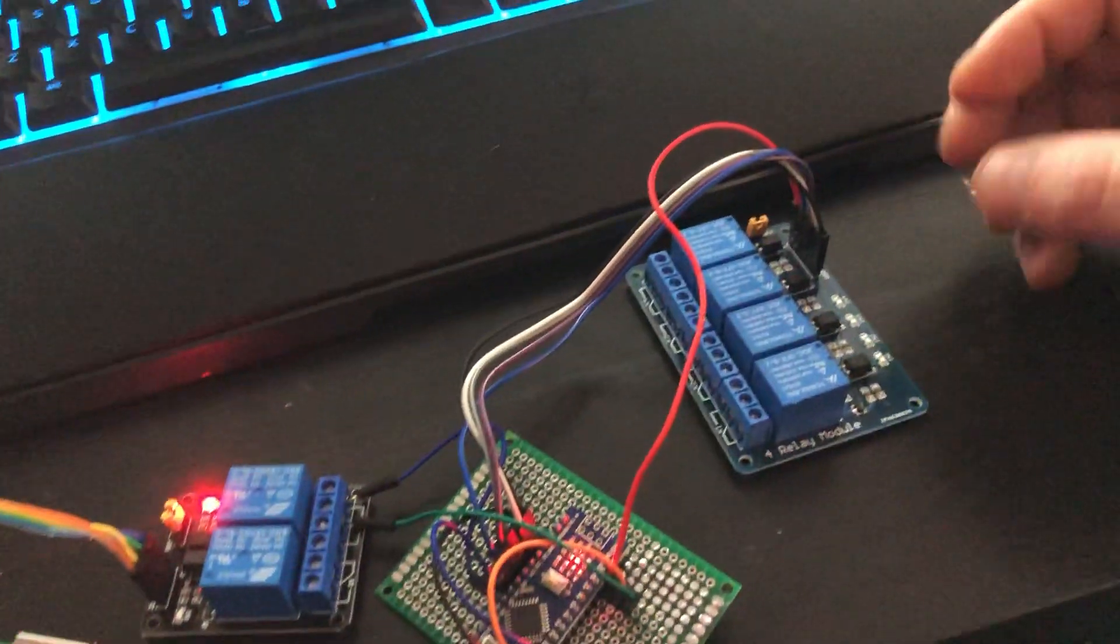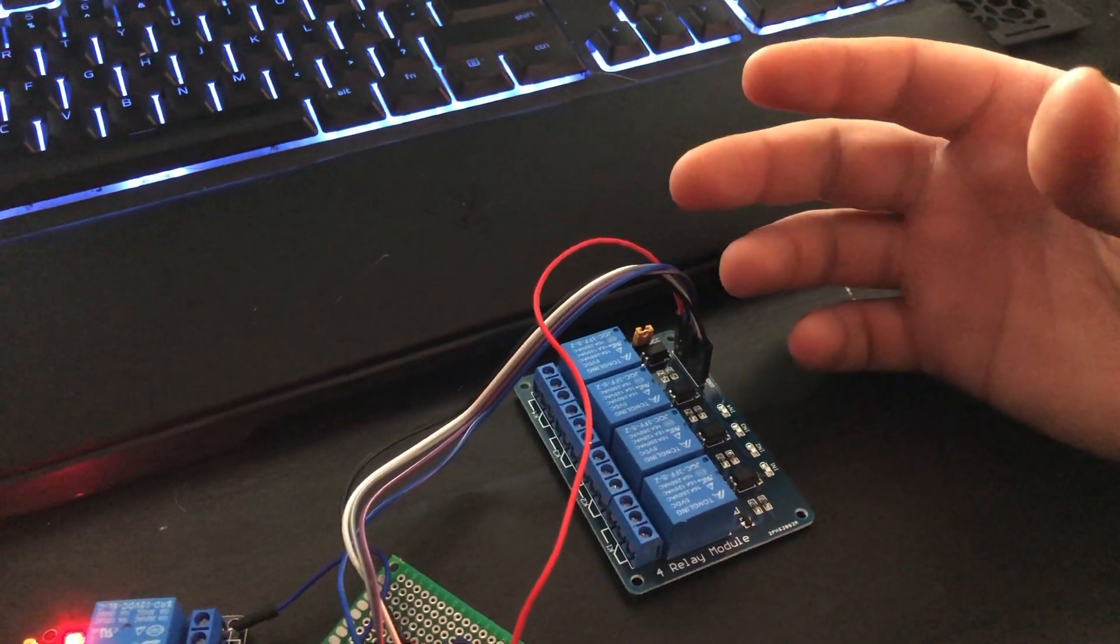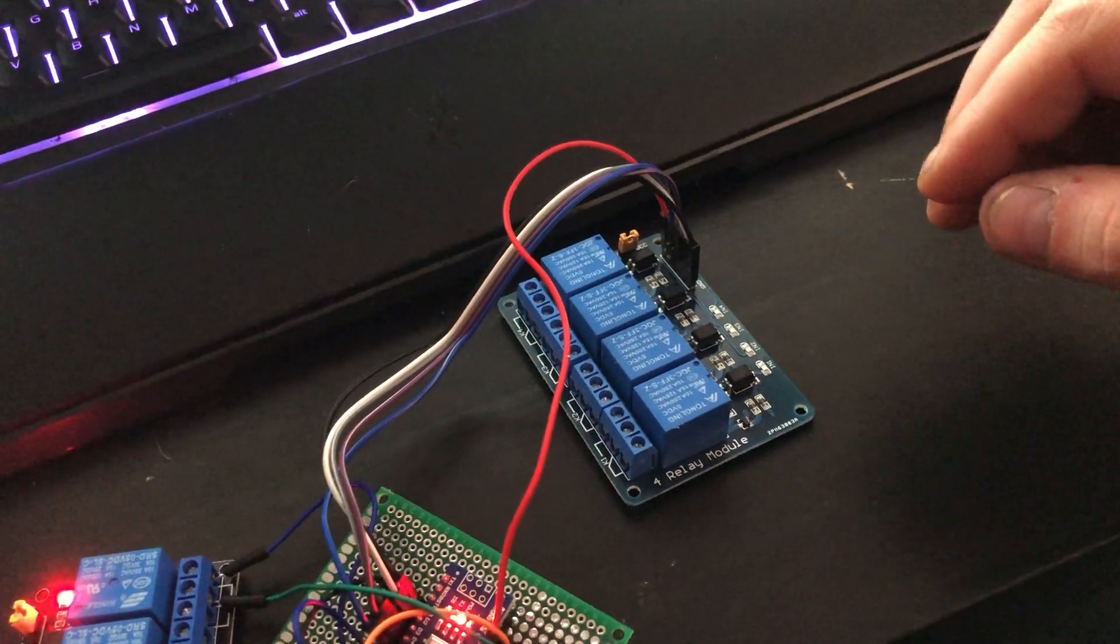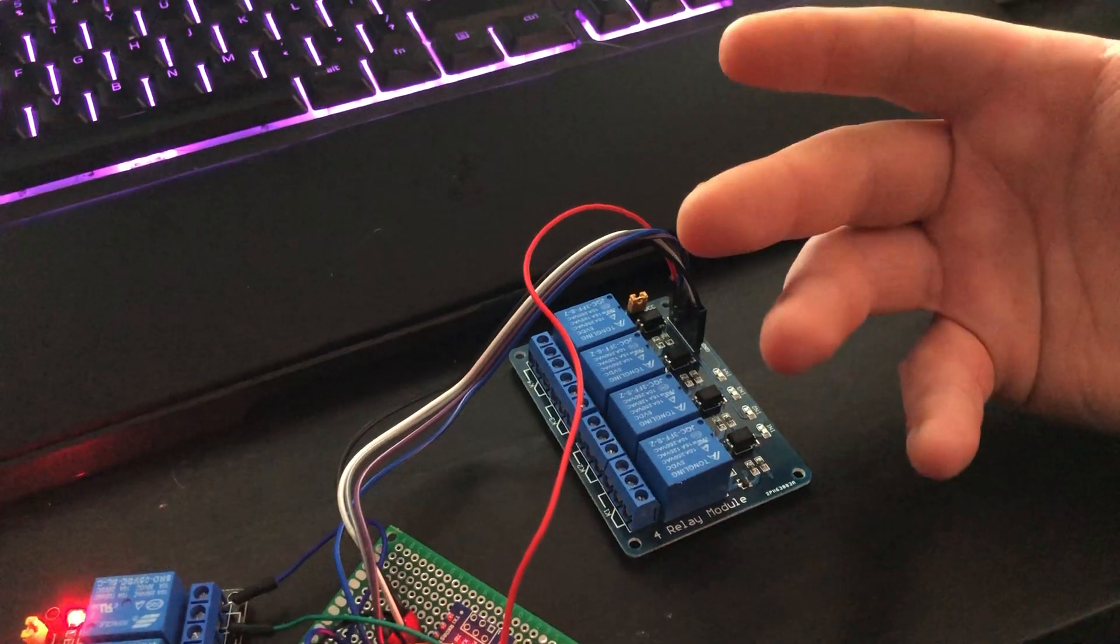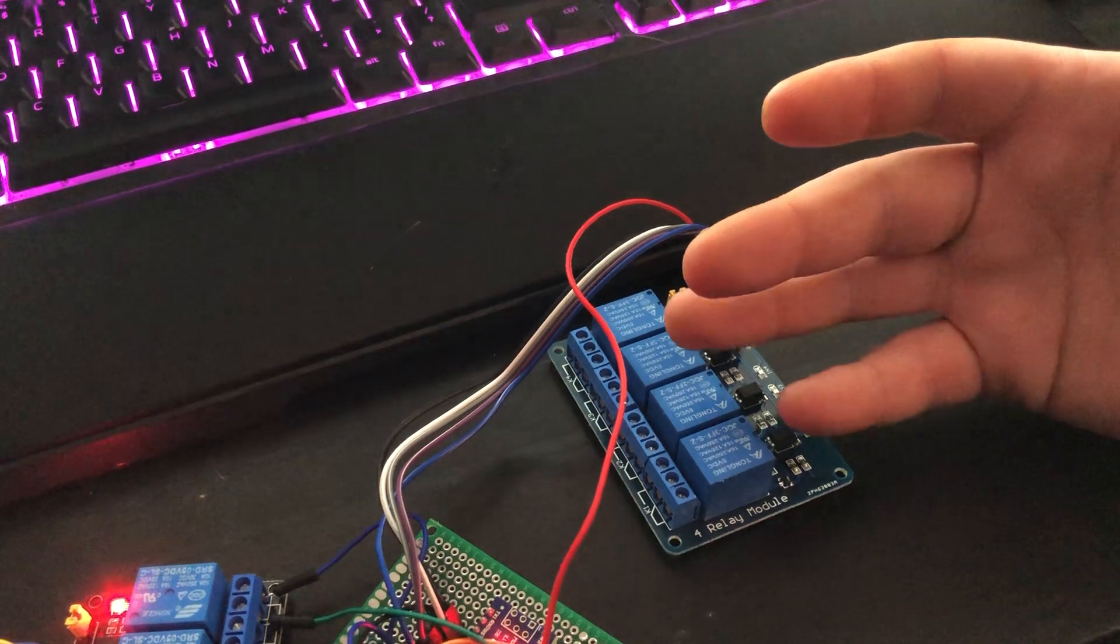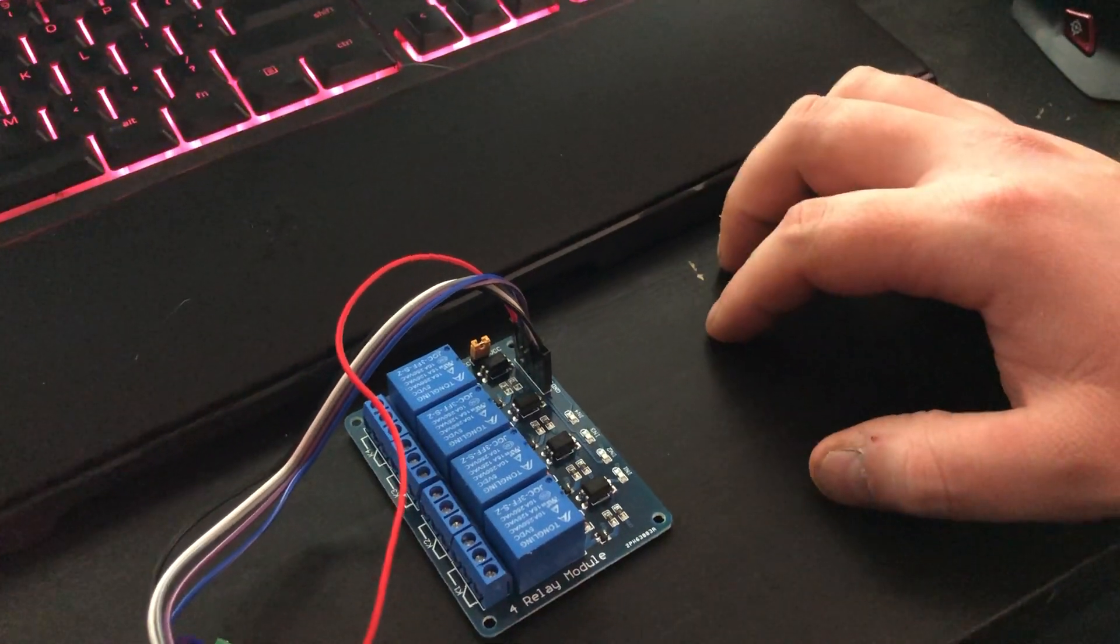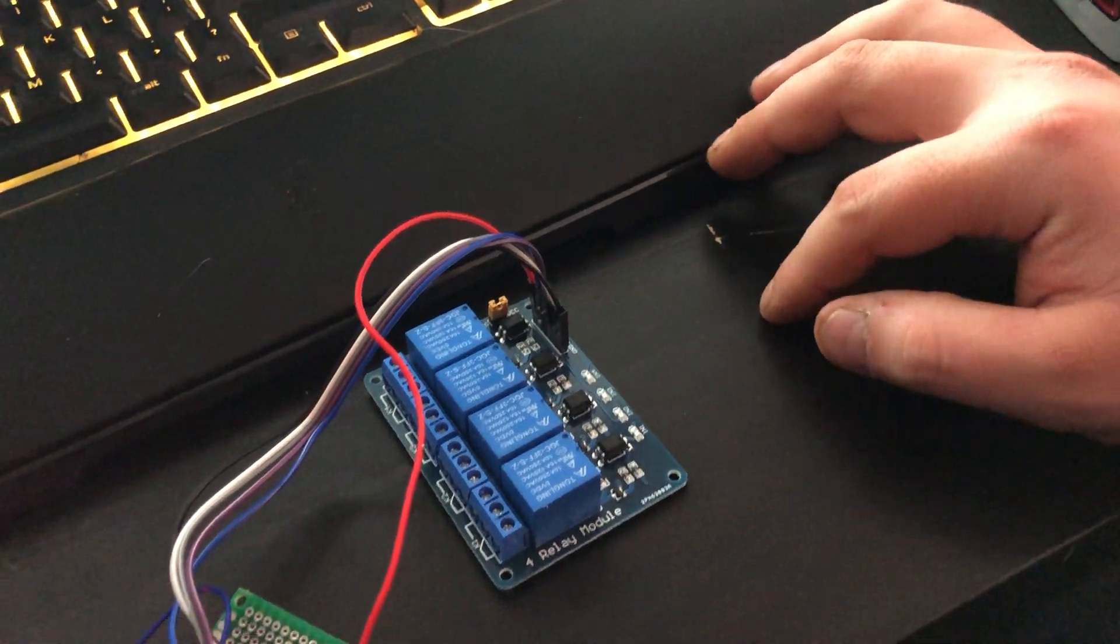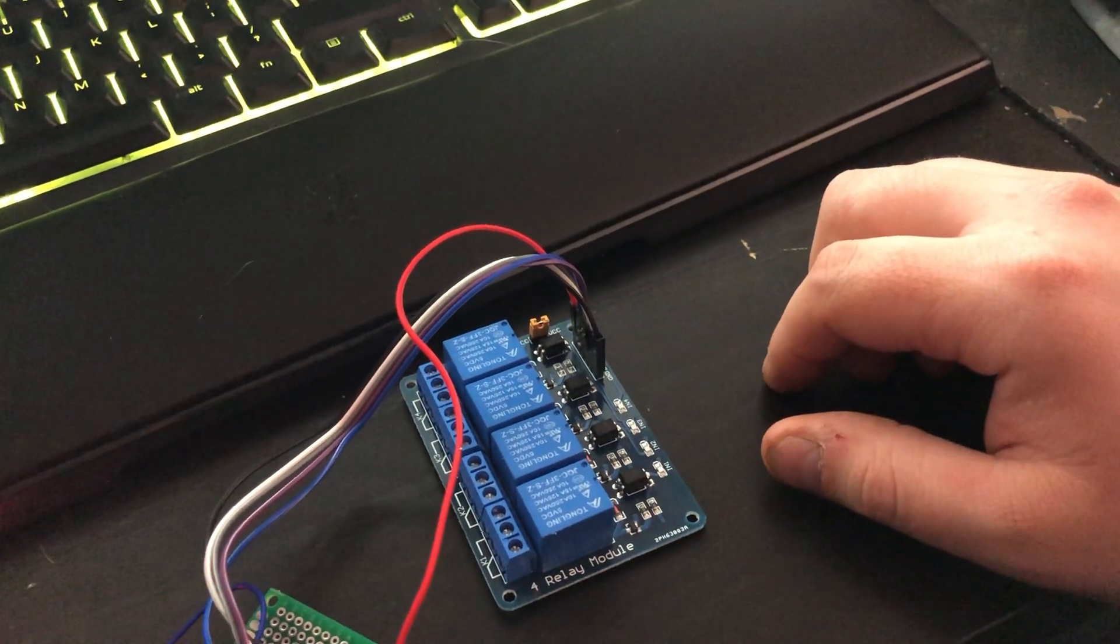So when it triggers the generator and the generator runs, then everything's hunky dory. The generator will stop. But if it triggers the generator and generator doesn't start because I don't know, it's out of gas or it's broken or whatever, what will happen is that your 712 unit will wait until the battery reaches 50% depth of discharge and just kill the inverter as a fail safe.